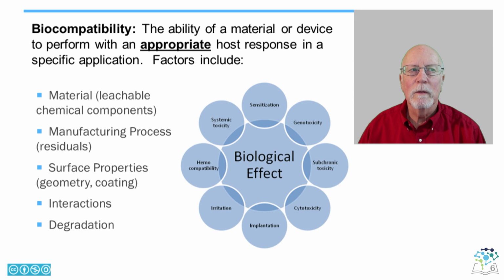Often manufacturers will assume that because their device is composed of materials that have historically been proven safe, they will require minimal testing. However, although the materials themselves may be safe, until we combine the potential impact of any chemical additives, coatings, unanticipated interactions among the materials, and potential degradation, in combination with any unexpected effects that the physical surface of the finished product may have on the biological system, we cannot claim safety according to these standards.